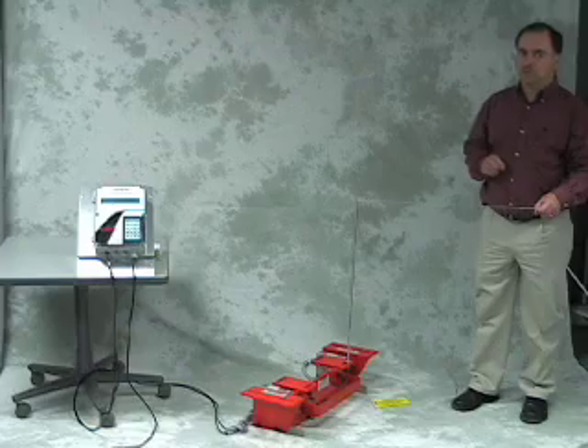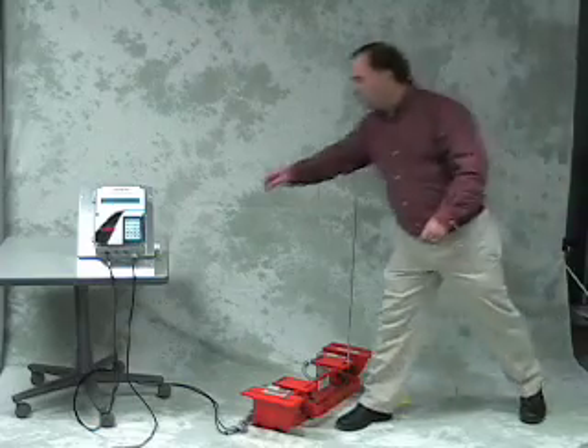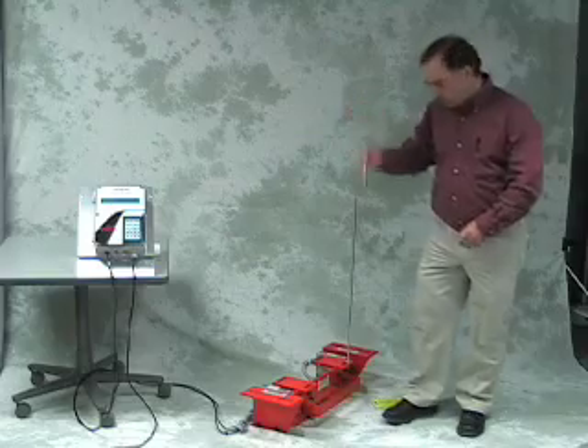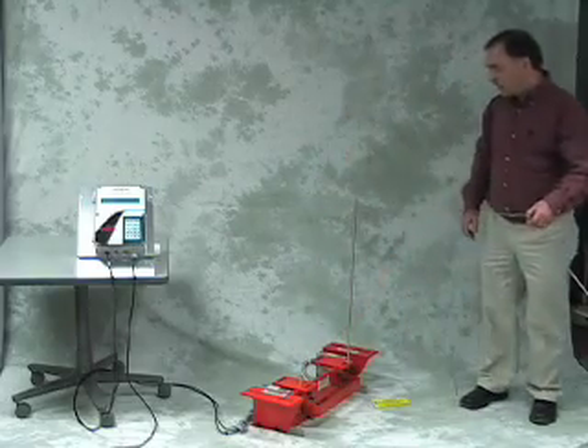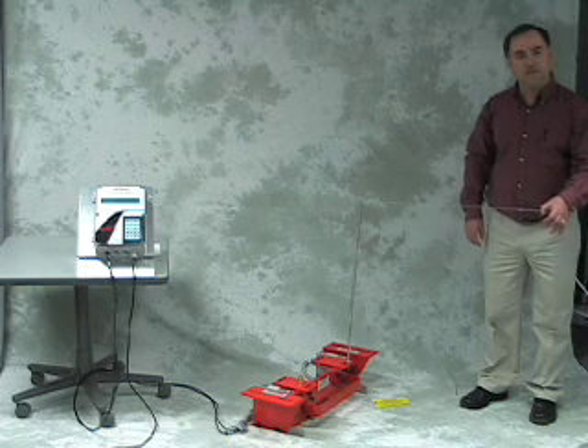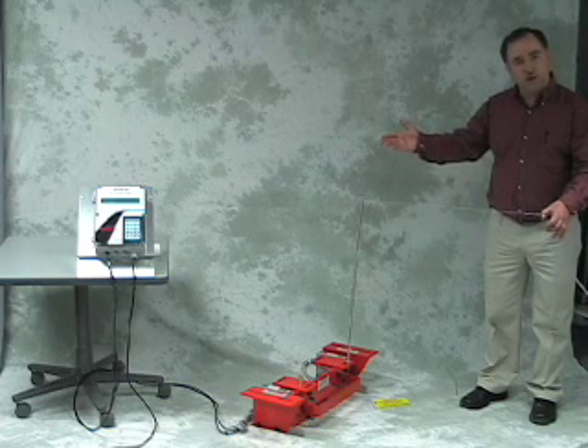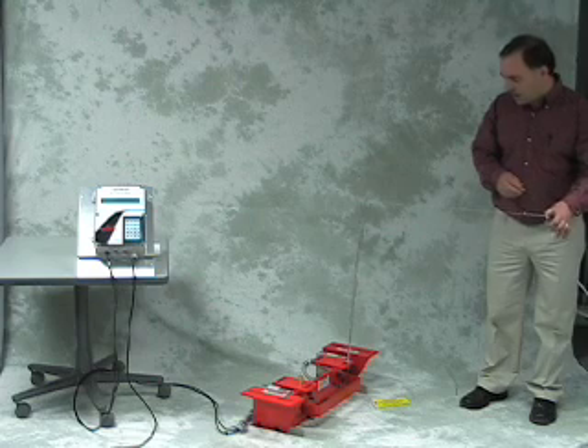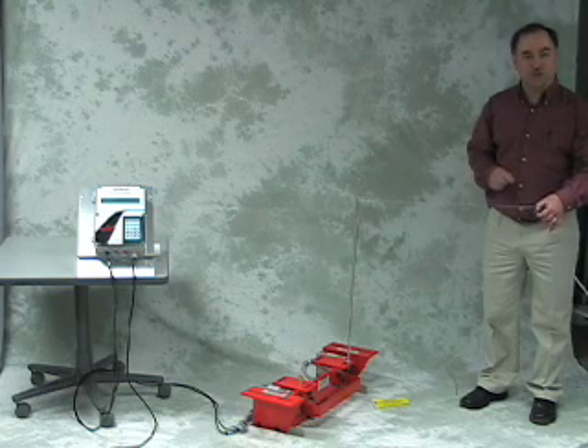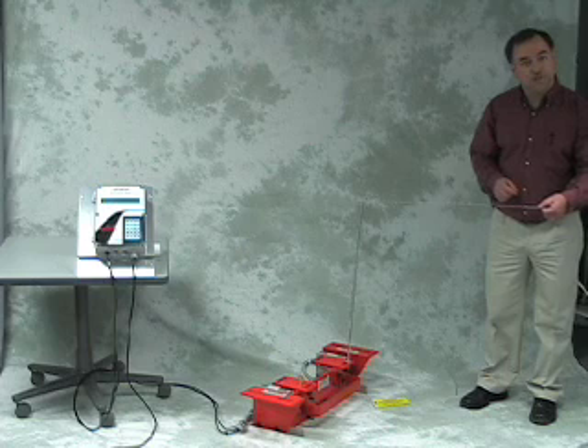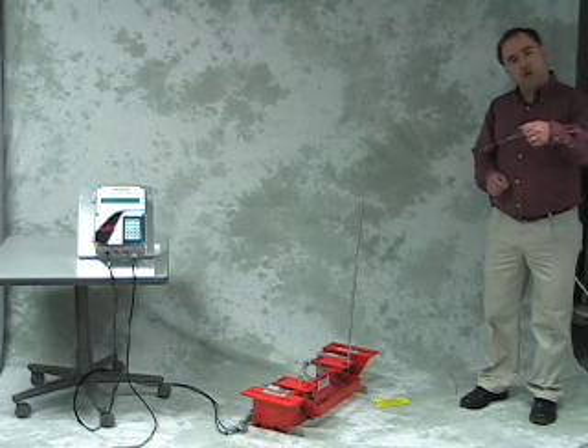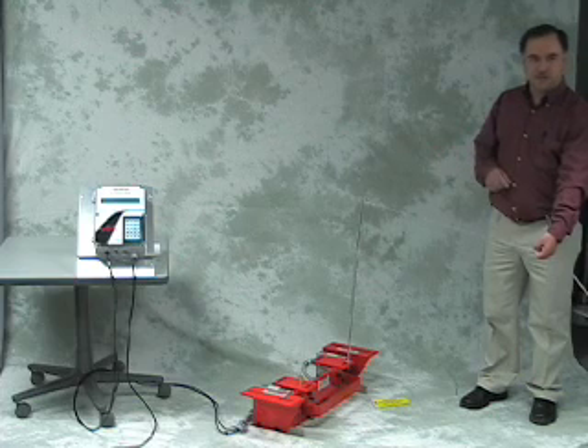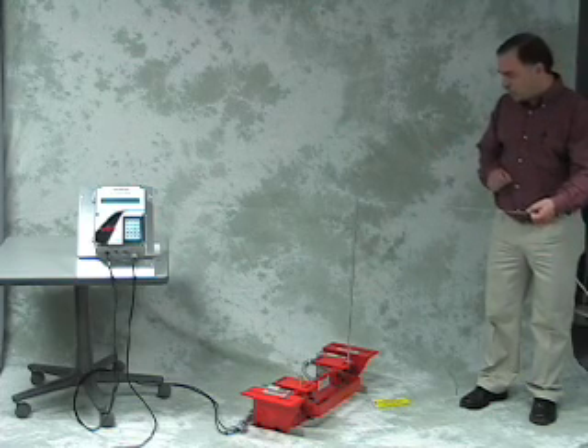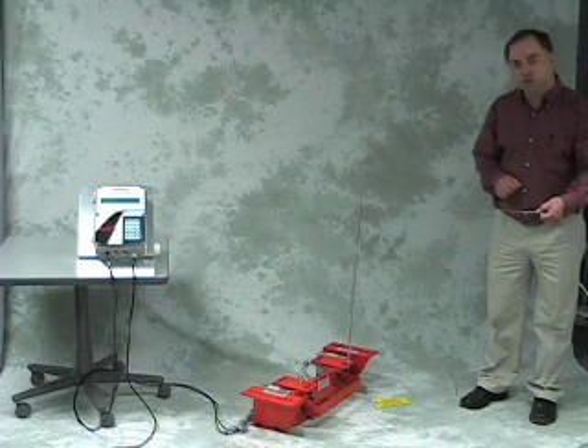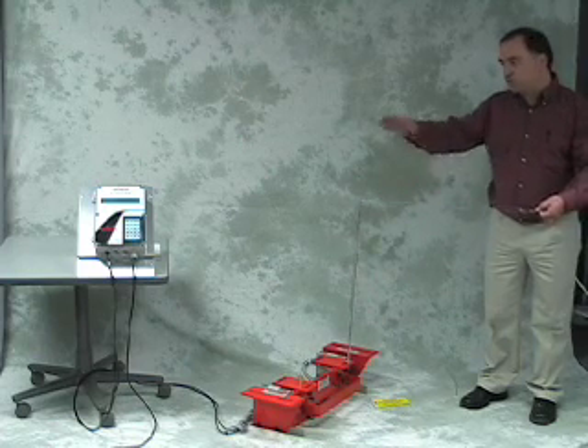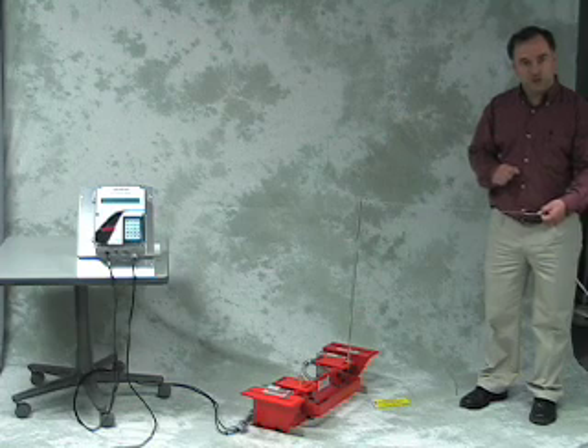They might not believe what they're seeing, so ask them to place the 100-gram weight back on the scale and pull with that same force again—they'll see the 100 grams displayed with no change. They still won't believe it, so let them pull on the string themselves. Show them that if they pull off the horizontal, there is a change in the display, but no matter how hard they pull or how much they bend the rod, there will be no appreciable change to the load display.